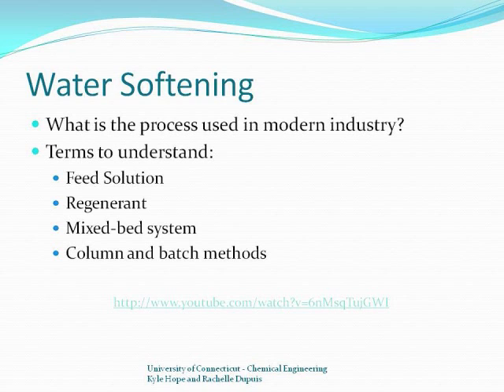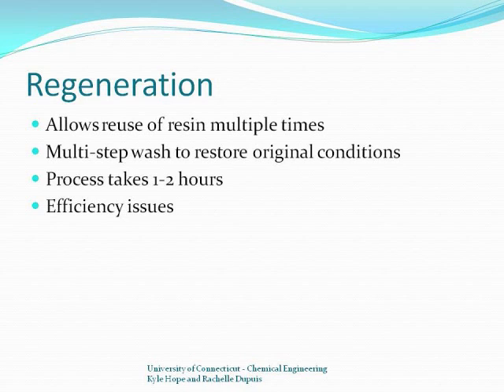However, this is very inefficient, and the prevalent technology uses a mixed bed column system where the feed solution passes through a series of separate cation and anion exchange beds. When it comes out at the end of the cycle, the feed solution is free of the unwanted ions and may even change in appearance, as seen in this YouTube video. Eventually, the resin reaches its exchange capacity and must go through the process of regeneration. Most systems utilize a computer system to determine when to start the regeneration process, which takes between one and two hours.